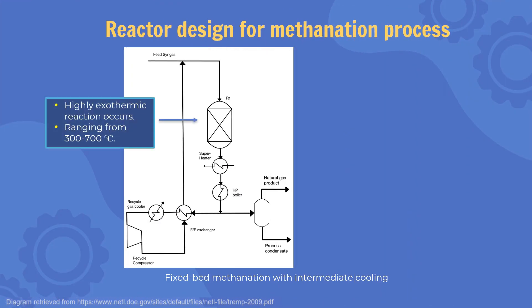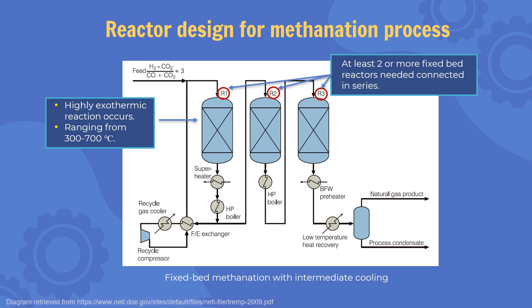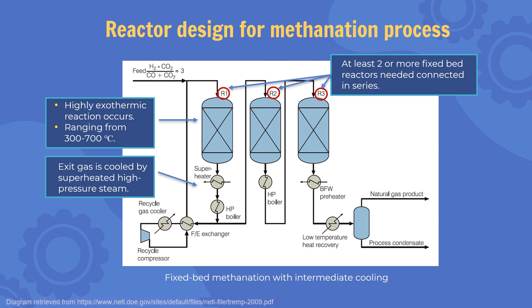Due to the strong exothermic nature of the methanation reaction, which ranges from 300 to 700 degrees Celsius, and limited radial and axial heat transfer in a fixed bed reactor, it is difficult to operate a single bed reactor under isothermal conditions. For good control of the reaction temperature, at least two or more adiabatic reactors must be connected in series. The exit gas from the first reactor is cooled by production of superheated high-pressure steam.